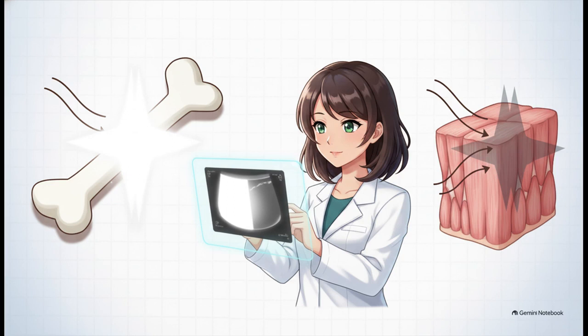When our sound wave hits highly dense tissues with very high impedance, like bone, almost all of the sound energy is reflected back. The machine registers this massive echo and slaps it on the screen as a bright white or hyperechoic signal. On the flip side, softer tissues with lower impedance differences let more sound just pass right through, creating weaker echoes that show up as darker, hypoechoic shades of gray. So the varying shades of gray you see on an ultrasound are literally a map of tissue densities.